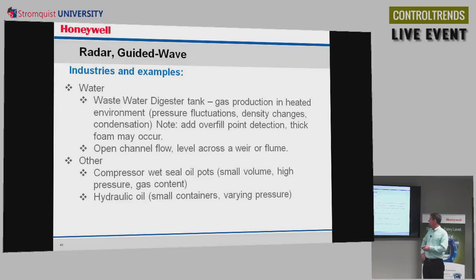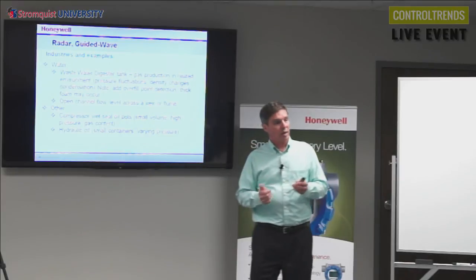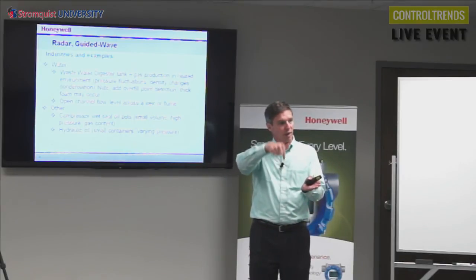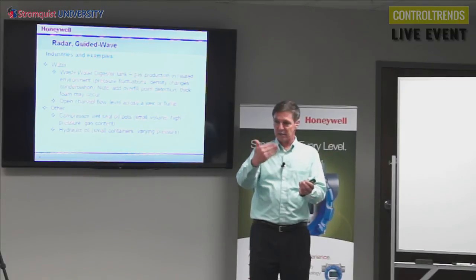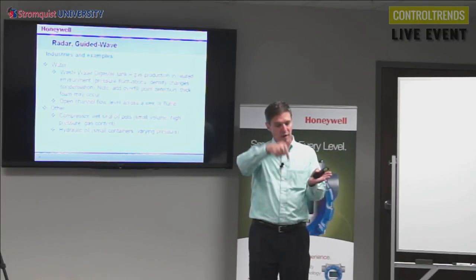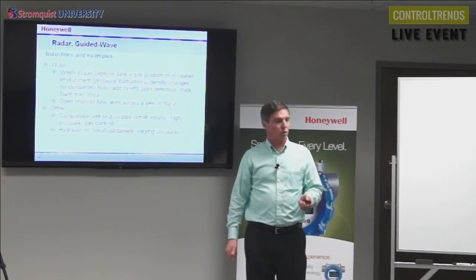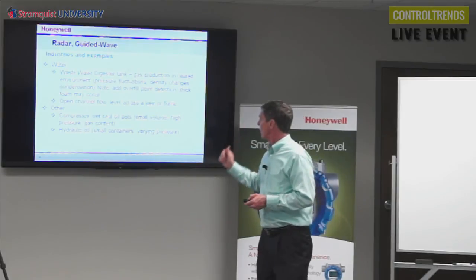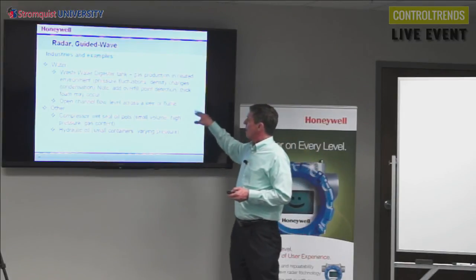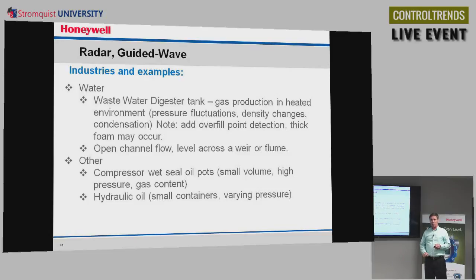Water applications for wastewater digester tanks. The second one is open channel flow. So this is if you have a very big body of water and you're flowing it from one area to another, you're going to go through something called a weir or a flume, open channel flow measurement. As you're going through this weir or flume, you're measuring the level across the notch. As that level changes, that changes with flow. So if you measure the level across this notch, that can give you flow. This is often done with ultrasonic, and I think we really want to note this can be done with radar, but because ultrasonic has traditionally been the way to do it, that's most often what people will do.